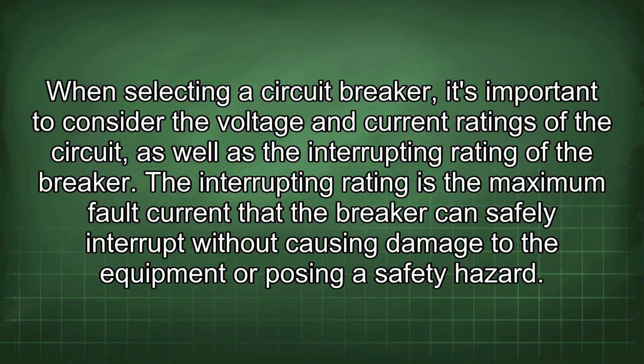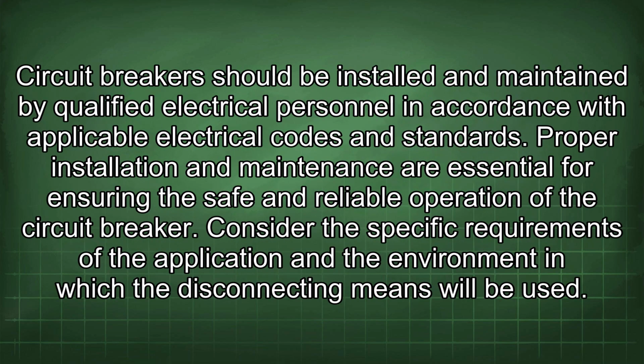When selecting a circuit breaker, it's important to consider the voltage and current ratings of the circuit, as well as the interrupting rating of the breaker. The interrupting rating is the maximum fault current that the breaker can safely interrupt without causing damage to the equipment or posing a safety hazard. Circuit breakers should be installed and maintained by qualified electrical personnel in accordance with applicable electrical codes and standards. Proper installation and maintenance are essential for ensuring the safe and reliable operation of the circuit breaker.